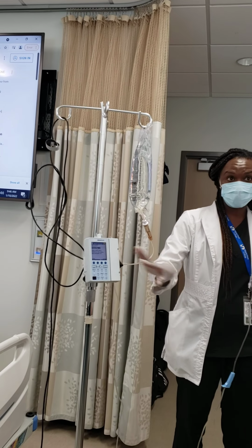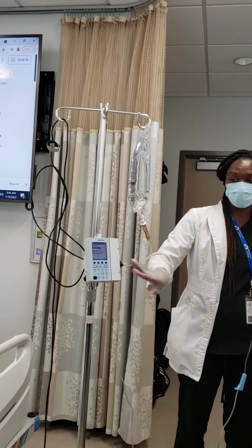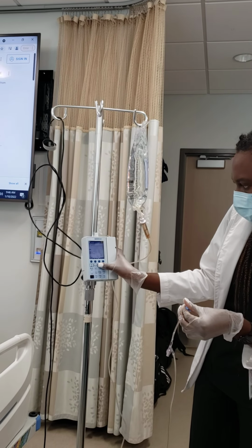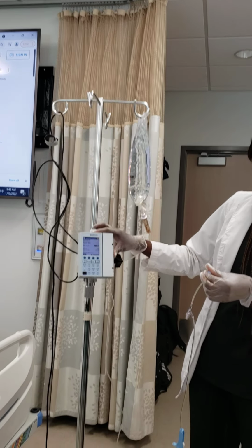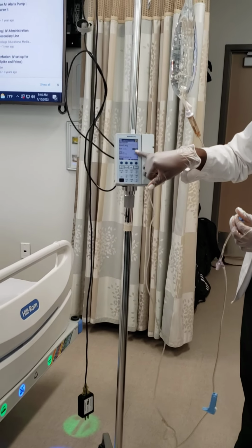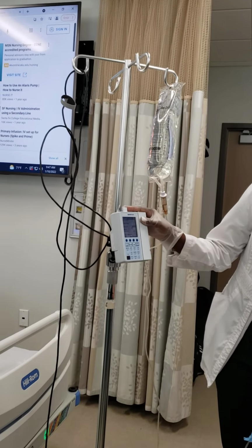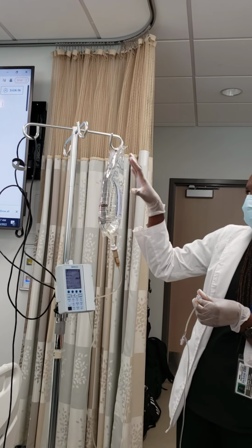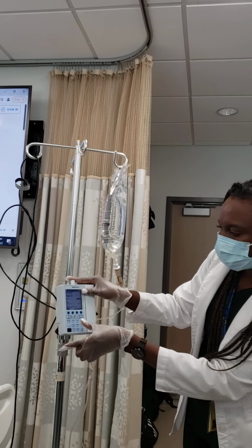Okay, only the pump has full control now. The pump is actually programmed to give how much fluid it's supposed to give. So now it tells you what it's going to do.